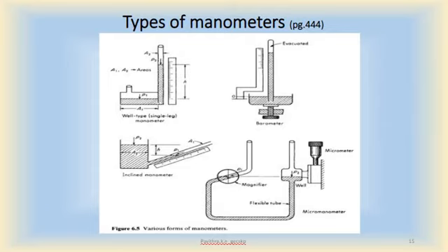So this pulse is recorded. The time taken by this pulse to travel to the top level of the column and to reach back is recorded, and depending upon the timing, the level difference is noted down. So such automated systems are also there for recording the pressure difference. They are more accurate than human-recorded systems.